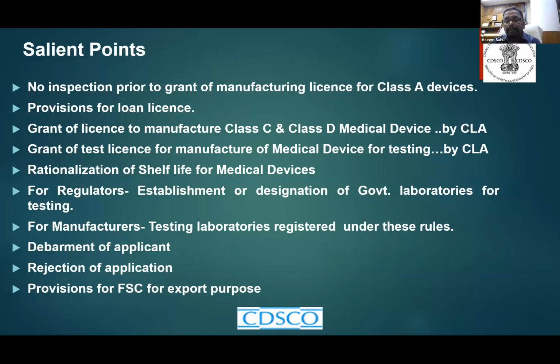manufacturing license. Test license to develop medical devices for testing purposes, because at the initial stage, without a license, no medical devices can be manufactured. If they want to develop the product, they need to take the license. So it is very difficult at the initial stage to obtain the license. So we have made that provision, where a limited quantity of medical devices can be manufactured or imported into the country for test and evaluation, and thereafter they can generate the data and submit it to the authority for necessary regulatory approval for commercialization of their products.